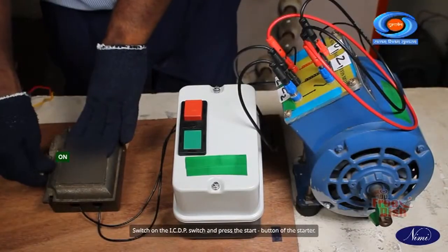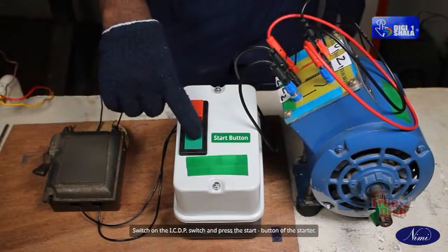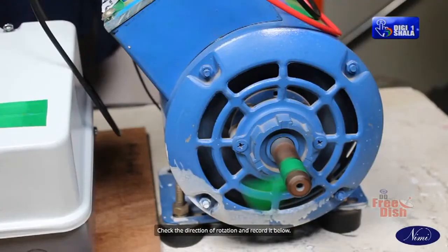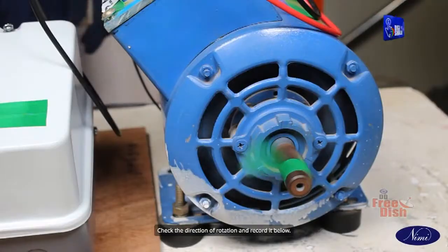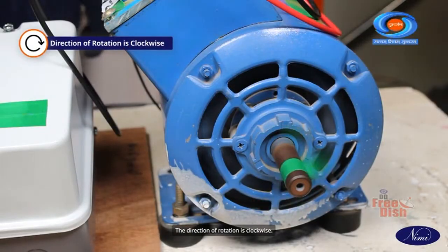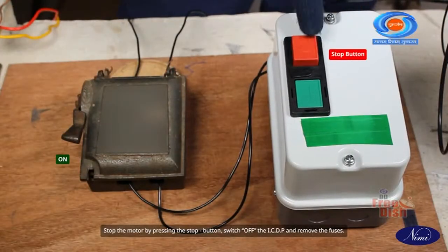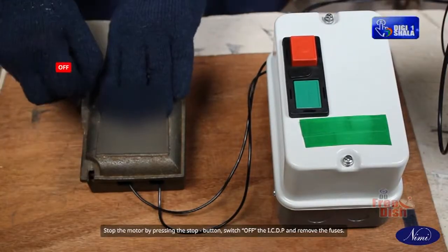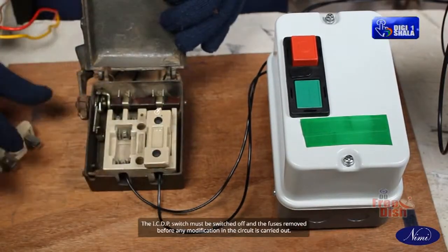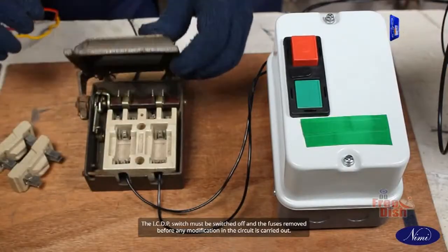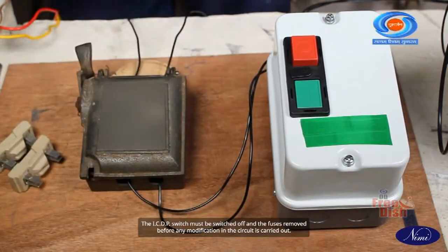Switch on the ICDP switch and press the start button of the starter. Check the direction of rotation and record it below. The direction of rotation is clockwise. Stop the motor by pressing the stop button, switch off the ICDP and remove the fuses. The ICDP switch must be switched off and the fuses removed before any modification in the circuit is carried out.